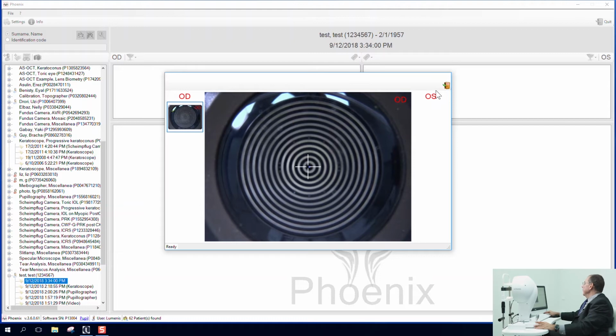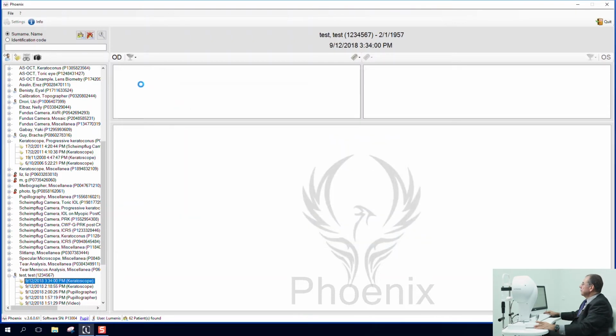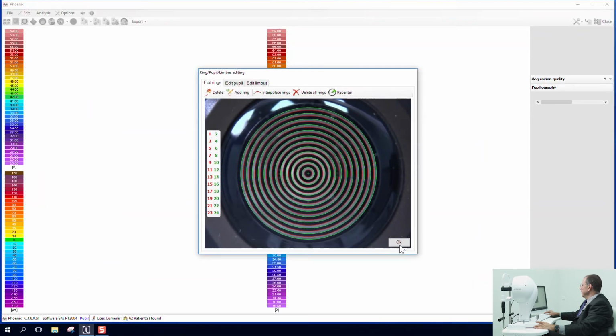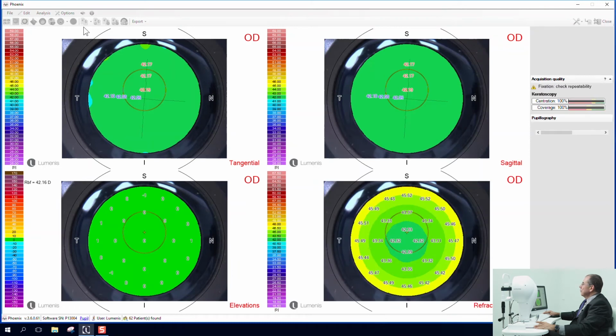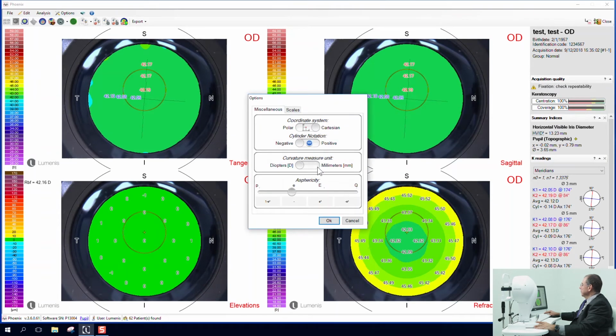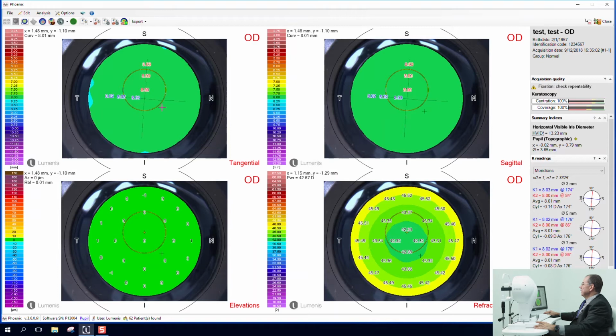And we have a reading. We don't have to do 3 readings, 1 reading's enough. And we're going to have a look at this. At the moment it's in diopters. We're going to change the scale to millimeters. And that would be pretty accurate. It's showing us 8.08, 8.03, 8.02, 8.04. We would like it to be 8 millimeters plus or minus 0.04. So we're actually within the calibration range. I believe that if we would clean the actual product, it would be perfect. But even so, we're going to do an actual calibration process for you.